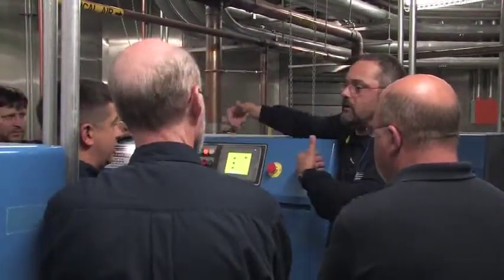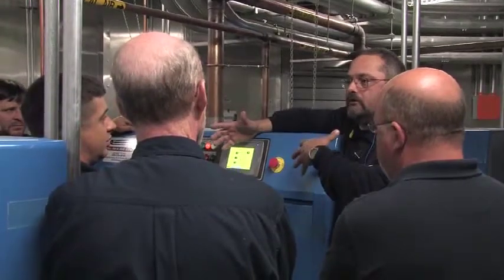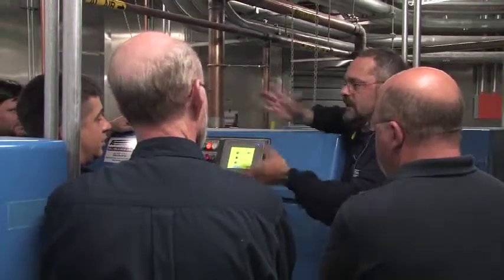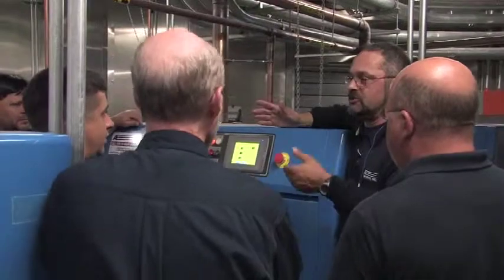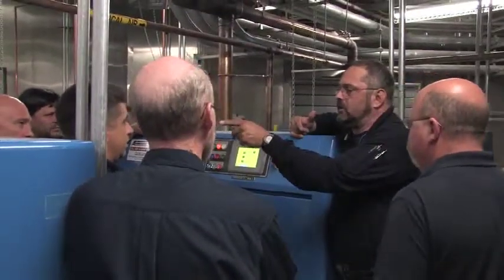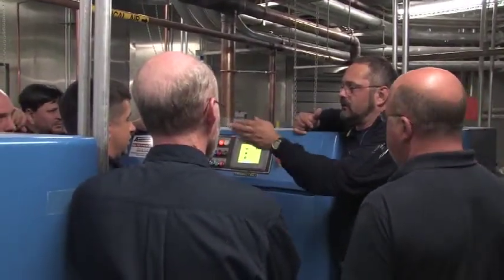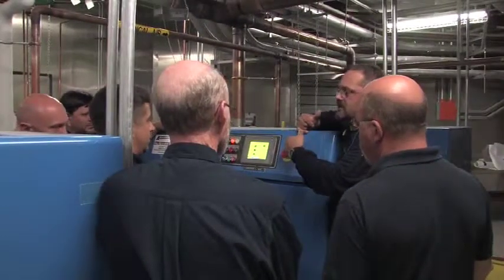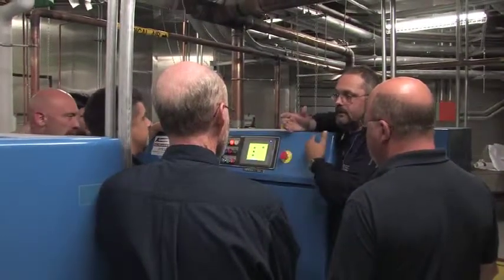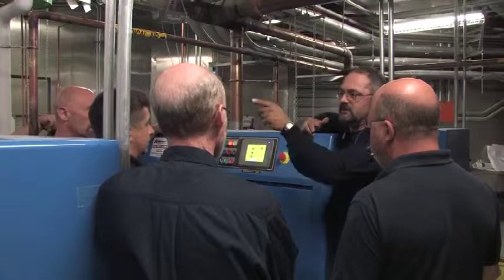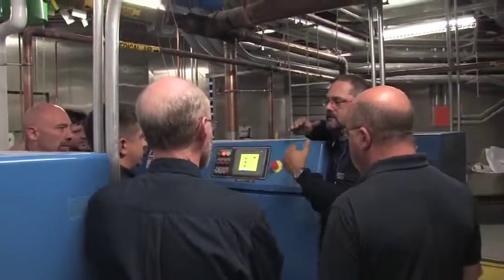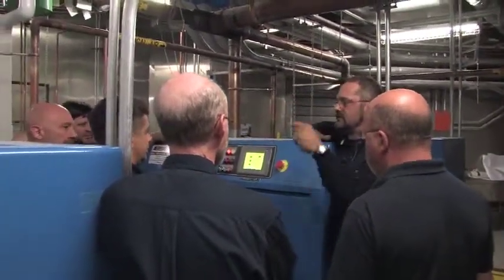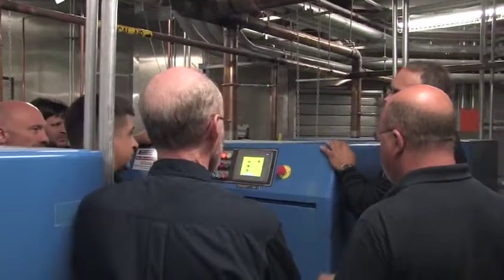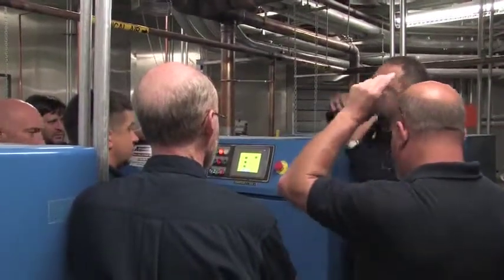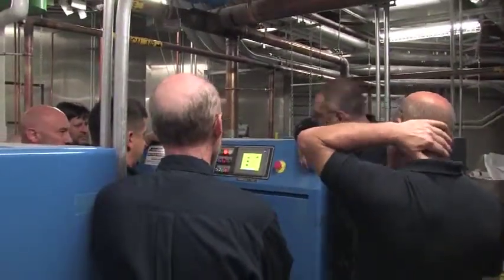Yeah, basically what we're doing here is the standard 2-unit lead lag, and I just rigged it so lead on this one or lag on this one is the same as lead on this one. So if that one's in the lead and this one says lead, they're still staggered. So if it's lead, lag, or vice versa, they'll still shift.